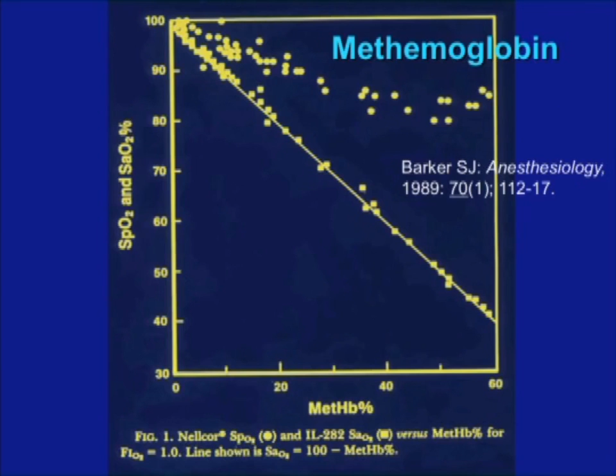And I scratched my head and thought, why is that? Well, let's think. It's the ratio of ratios. With methemoglobin, remember, it's turning the blood brown. So I'm adding a large absorbance. I'm adding a number to both the red and the infrared. In other words, I'm adding a number to both the numerator and the denominator of a ratio. What happens to a ratio when you add large numbers to both the top and the bottom? It drives that ratio towards 1. Go back to that calibration curve I showed you and look up a ratio of ratios of 1, and guess what? It's a SAT of 85%. So I published this conclusion in 1989, and it was verified by a number of clinical case reports.